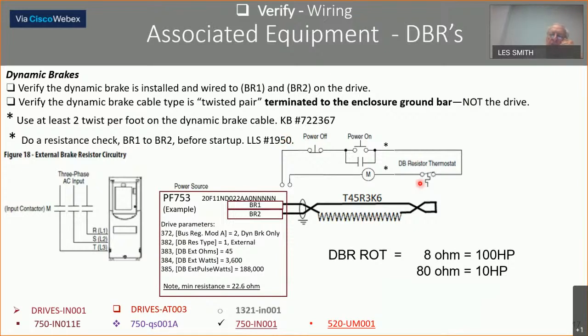Here's that temperature snap switch that comes inside of the dynamic braking resistor that nobody uses. And this is how it's supposed to be used. It's supposed to go to a starter contactor, and that is supposed to power the drive up. If the snap switch gets too hot, it opens up, takes power away from the drive.